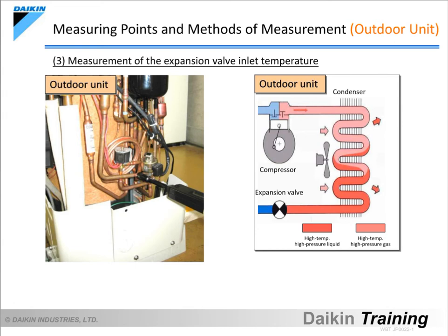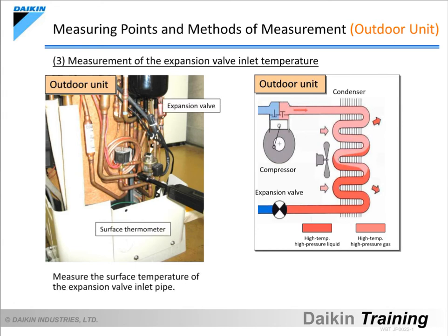Let's now measure the expansion valve inlet temperature. Measure the temperature at the inlet pipe of the expansion valve on the outdoor unit with a surface thermometer. The expansion valve inlet temperature reads 113 degrees Fahrenheit.